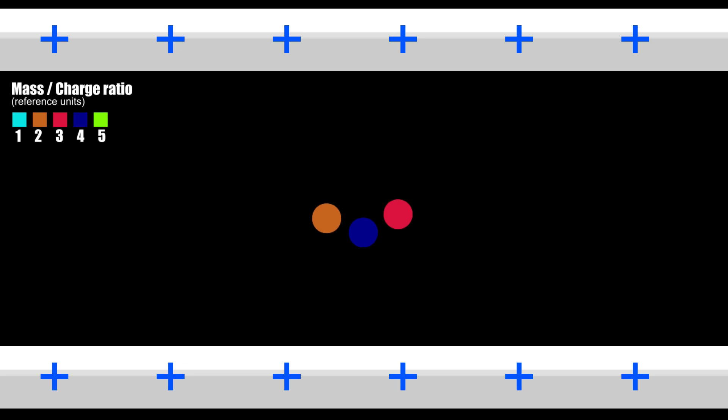When the ions are in the middle of the rod, the repelling forces from the two positive rods somewhat cancel each other out in the middle of the tube and the path of the ions will more or less not be affected. If the ions are off-center, the repelling forces from the two positive rods will be unbalanced, creating a net force that will force the ions towards the center. Because of inertia, less massive ions or more precisely ions with smaller mass-to-charge ratios will be pushed towards the center line a lot faster than ions with bigger mass-to-charge ratios. And this time difference is the key for detecting specific molecules based on their mass-to-charge ratio.